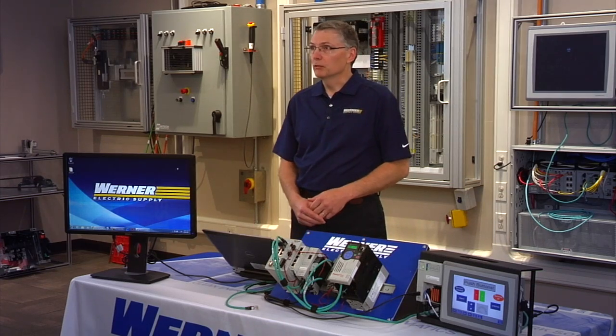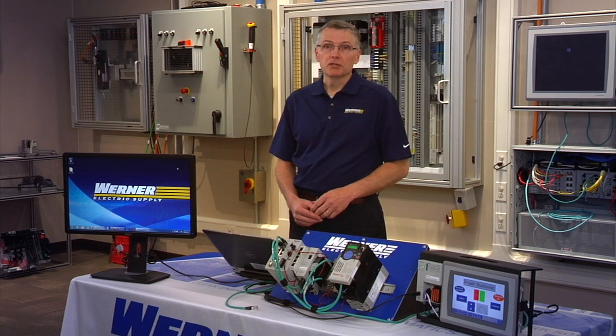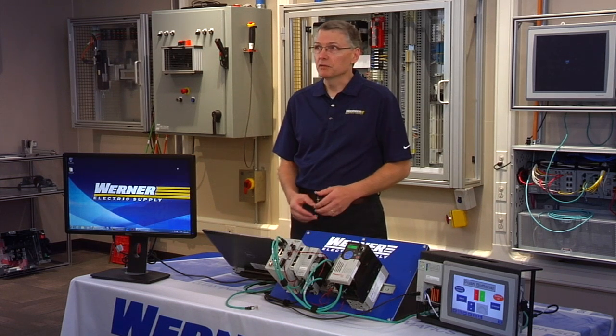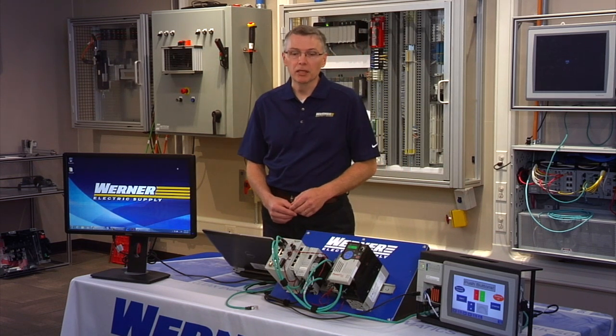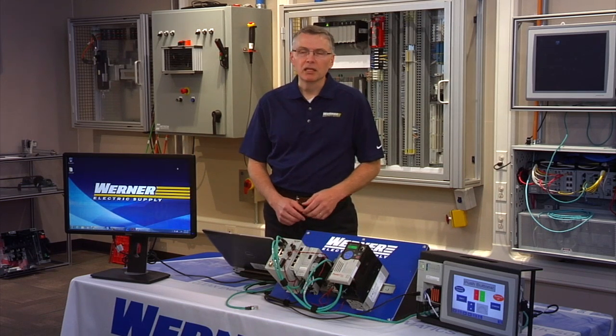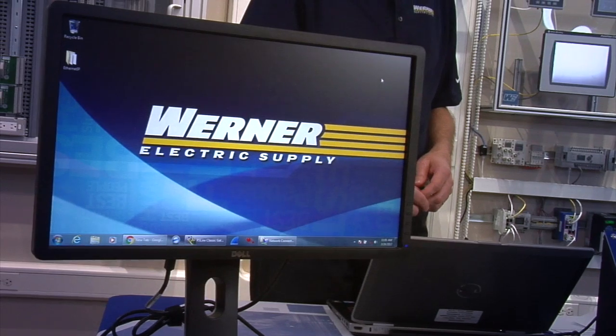So to get that we run it through Rockwell's express setup which executes a global macro, and that global macro enables certain parameters in the switch that will optimize it for a Rockwell Ethernet IP network, such as enabling the IGMP snooping and spanning tree protocol and other things.